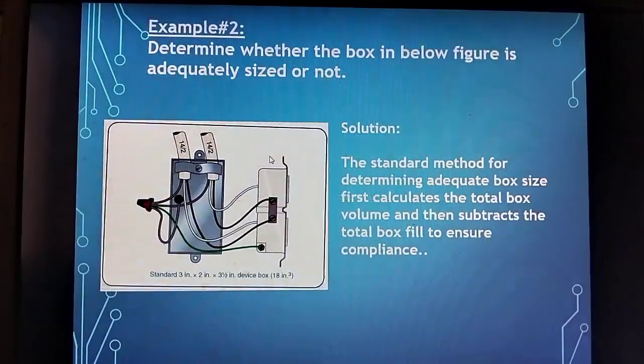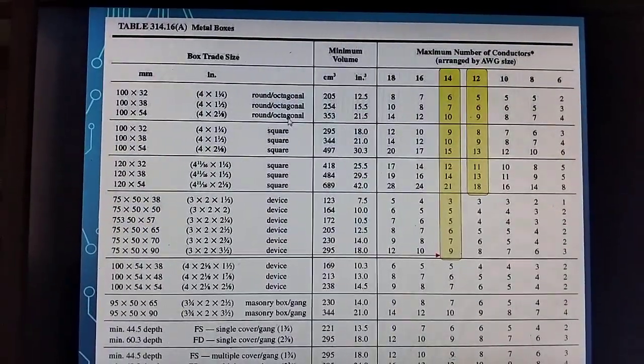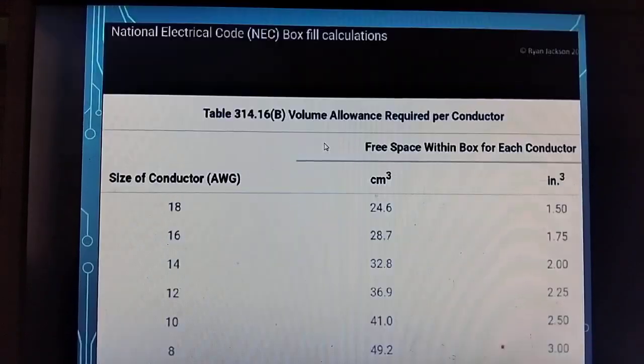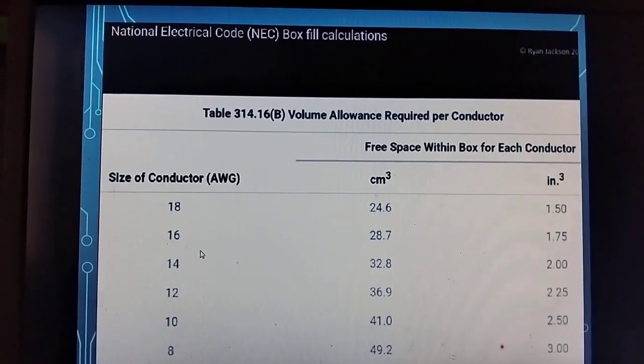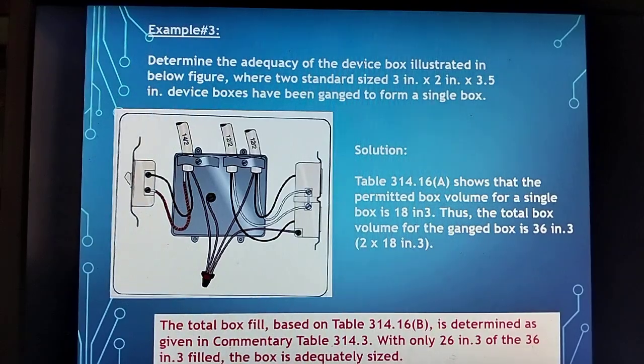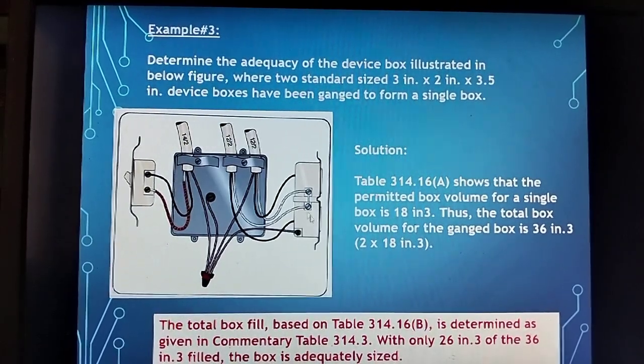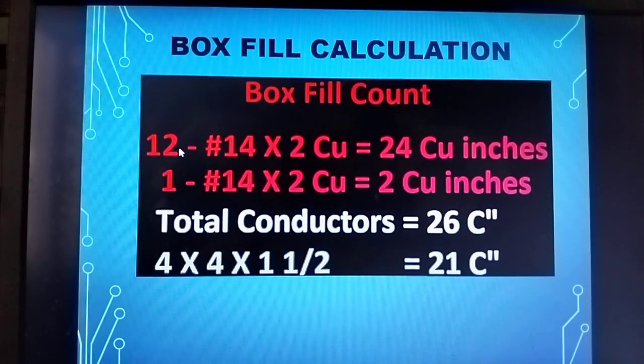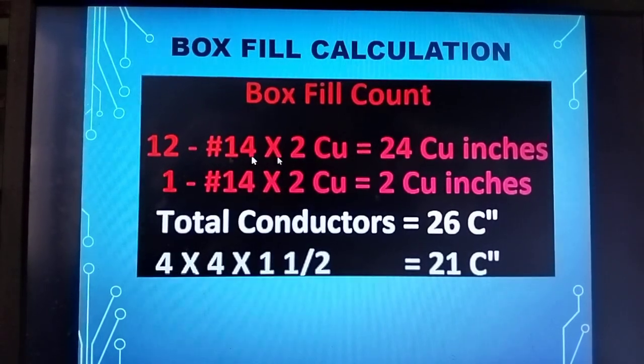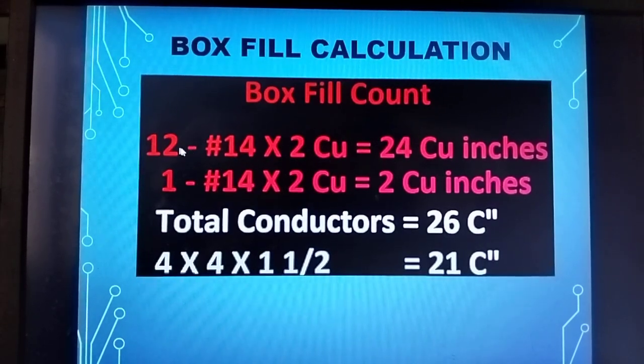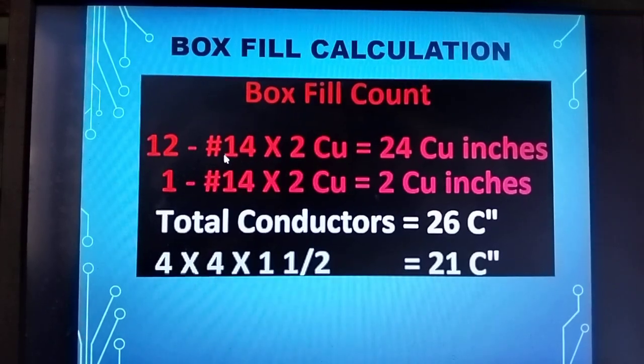Let's go back to the table. Size 14 has 2 cubic inches volume allowance per conductor. If it is size 12, 2.25. Okay, we go back again here. Say size 14, 12 pieces, so 2 cubic inches per size 14 times 12 equals 24 cubic inches.